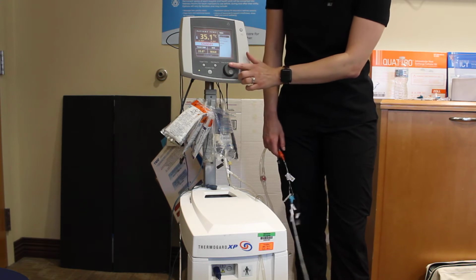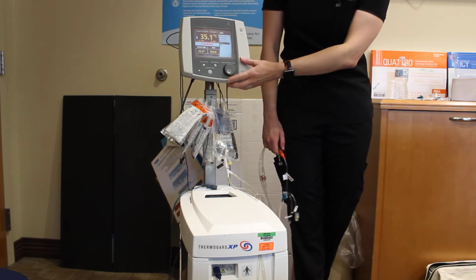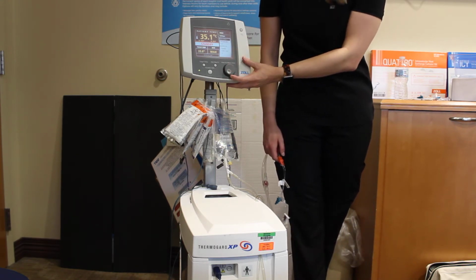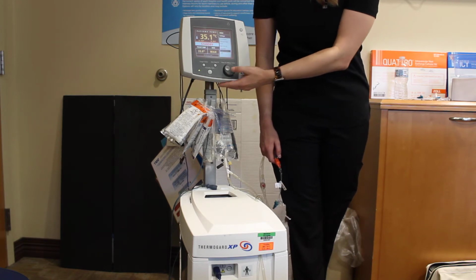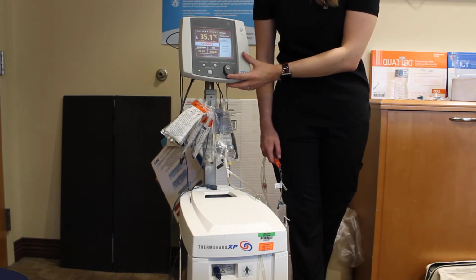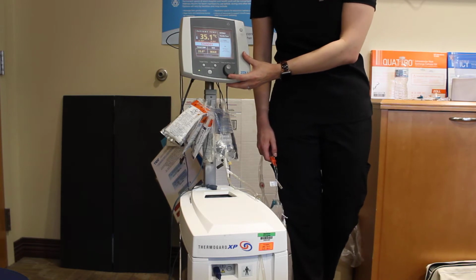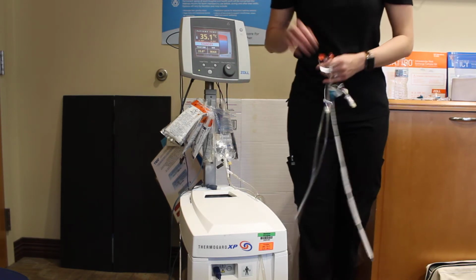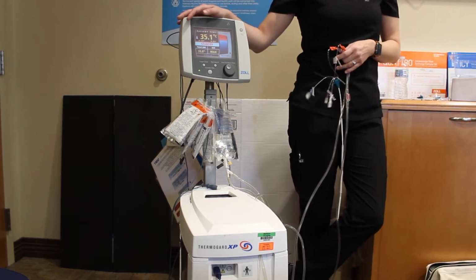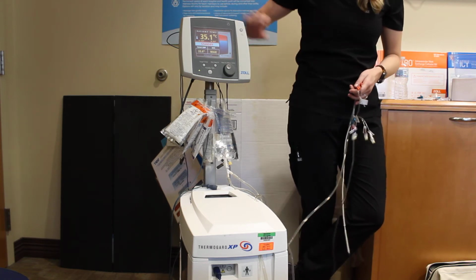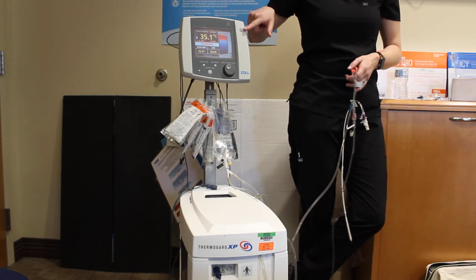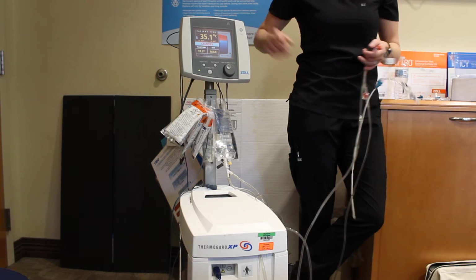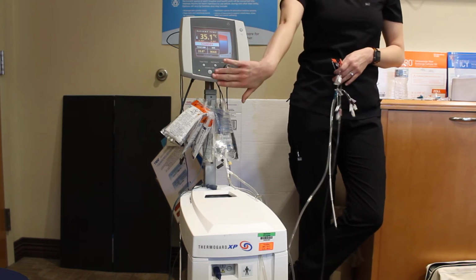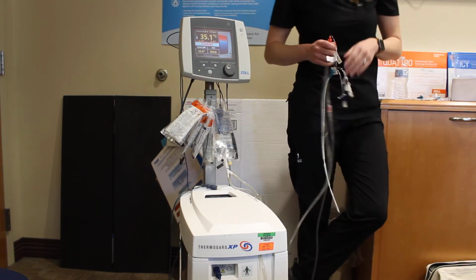So you'll press this button to get to the menu setting, you'll go down to settings, just like we did with the other alarms, and down to standby timer, and you can set the alarm for 15 or 60 minutes, so we'll put it on 15. If you're not back by then and somebody is really tired of this machine beeping, they can just walk in the room and press that little silence button, and it'll silence it for 15 minutes. It's just to remind you to make sure that this is going when you get back up from CT.